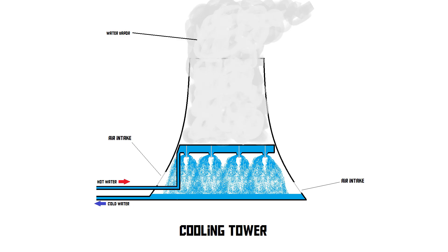A lot of water will evaporate inside the cooling tower, and the water vapour exits at the top. The cold water reaches the bottom and is pumped back into whatever we're trying to cool. We are evaporating a portion of the water, so we do need to keep refilling the system from a water source such as a river or lake — but the biggest part is reused. Some cooling towers also use fans to accelerate the airflow from bottom to top, creating even more wind along the droplets for an even lower relative humidity.